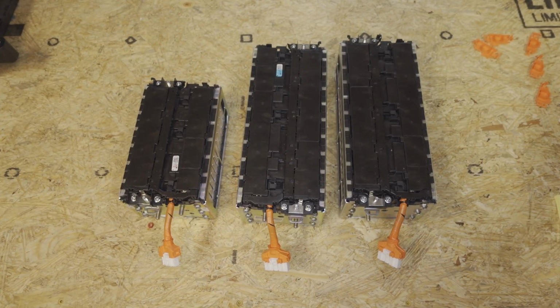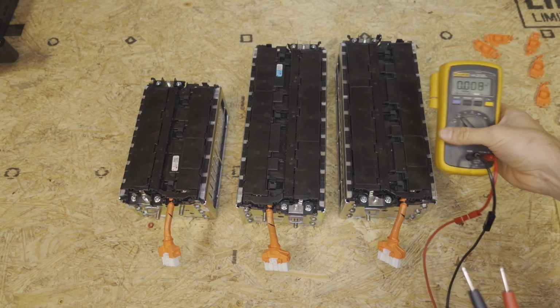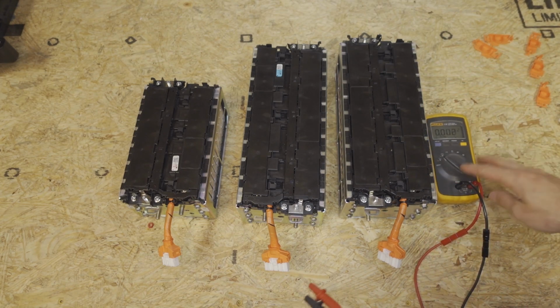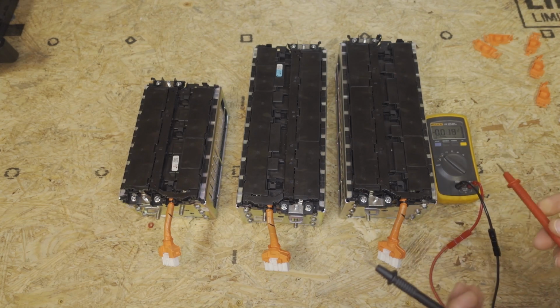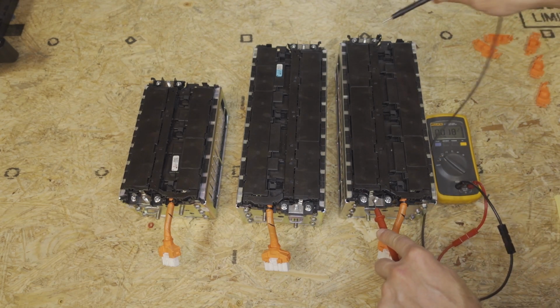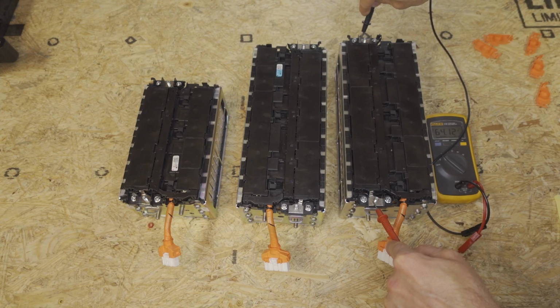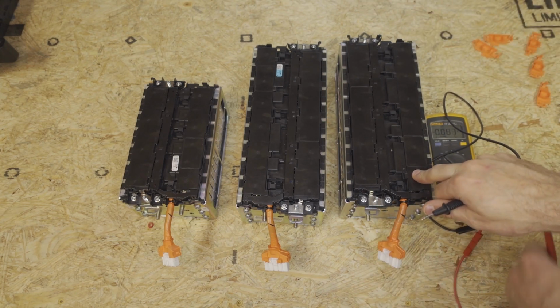Next, we measure and mark the polarity. I'm using a DMM set to at least 70 volts on the range, and we're going to measure each module from one side to the other. In this case, I'm measuring 64 volts positive, so this is an 18S plus module.